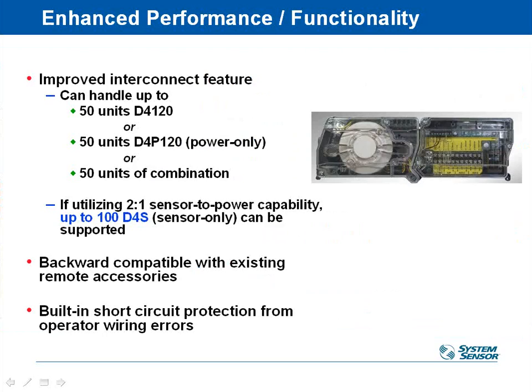You can interlock these detectors to each other. So if I have, say, 5 air handlers in a space and one of them goes into smoke alarm, maybe I want to shut down all 5 of them. I can definitely do that with interlock wiring, and I can interlock up to 50 of these off of each other. So one of them can shut down all 50, and then obviously you can see which one is in alarm by going to its associated remote test station or by looking at the detectors on the duct themselves and seeing which one has the alarm light on. So it should be easy to figure out which one actually went into alarm and not have to check all 50 of them.